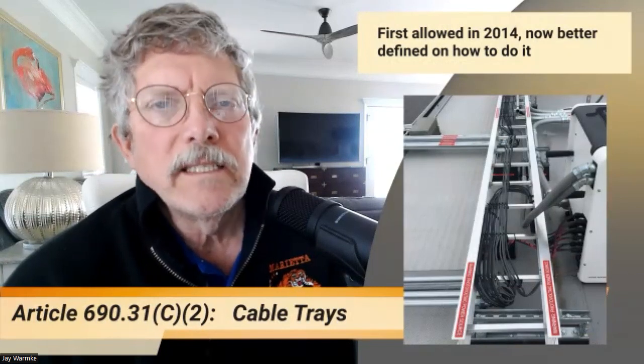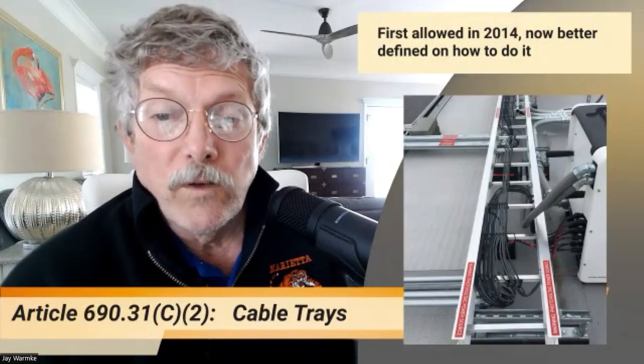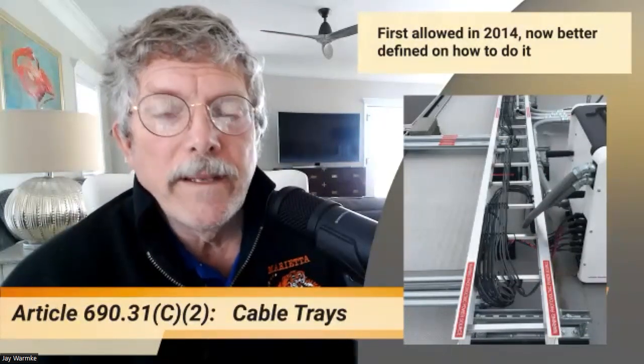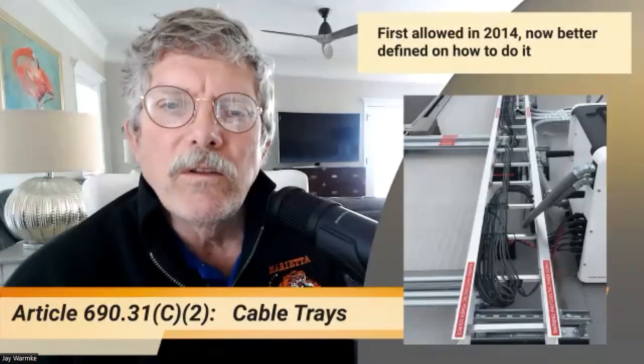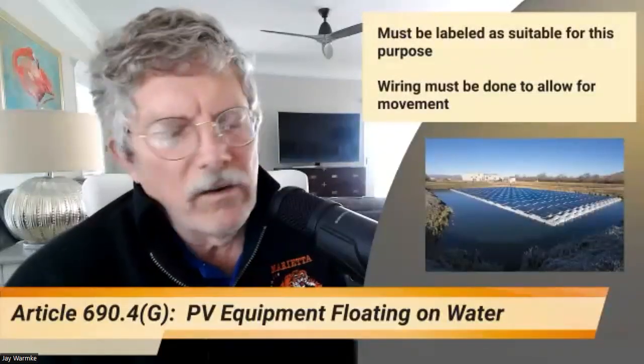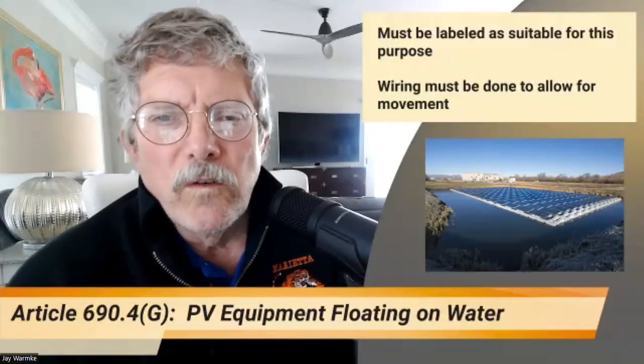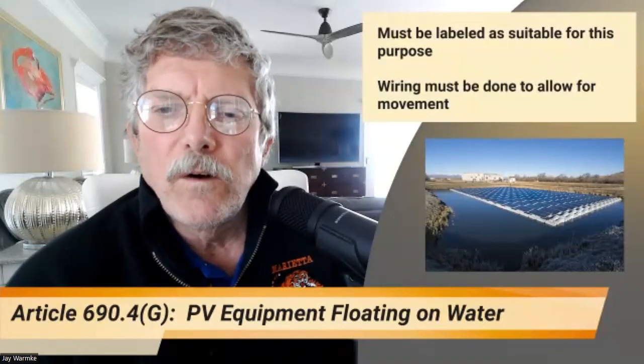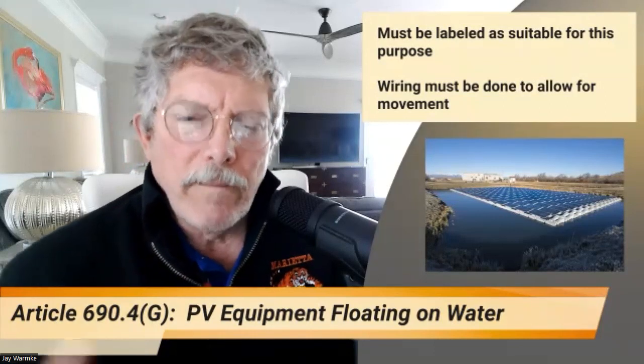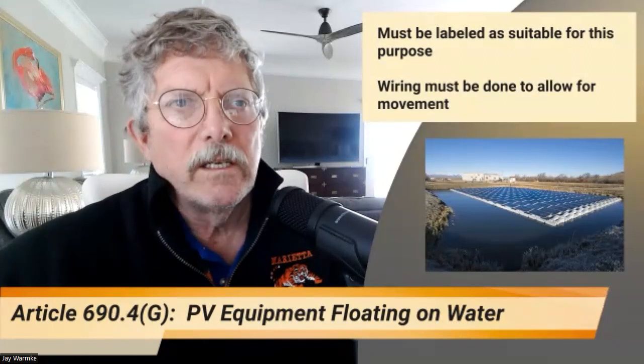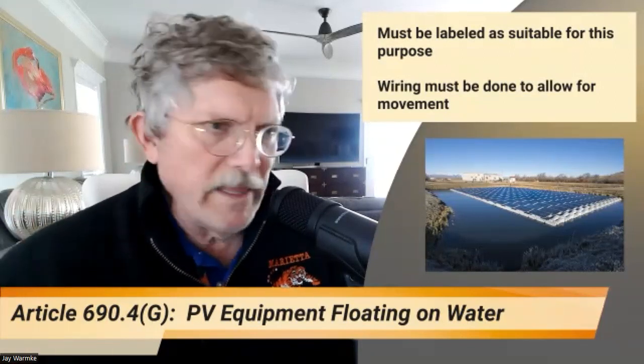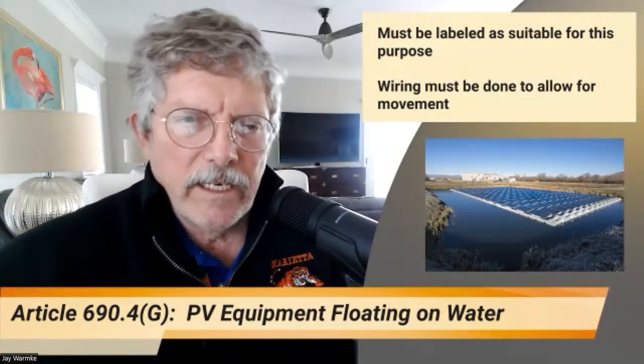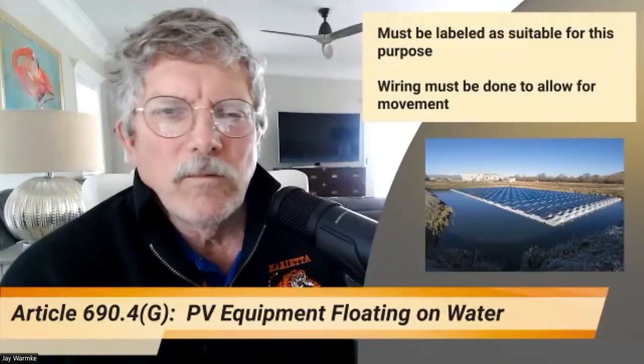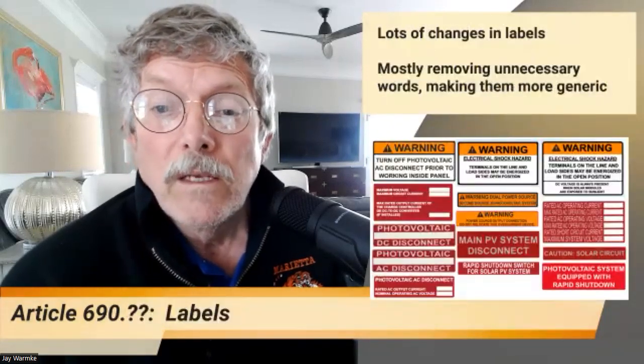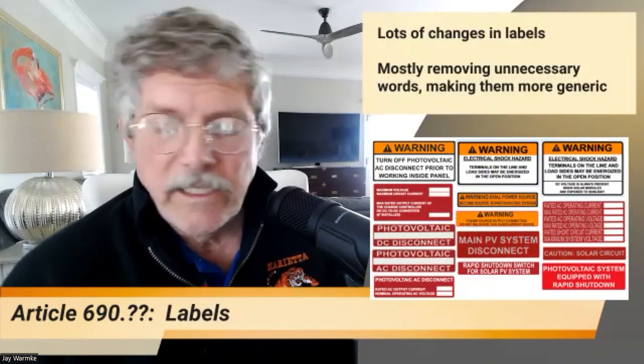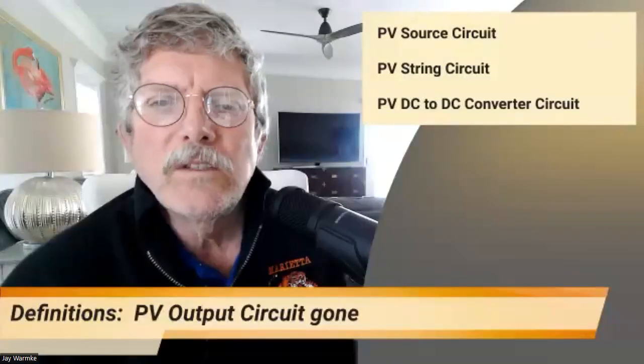They also got into cable trays and discussing how you would install cable trays for photovoltaics. Prior to 2014, we weren't allowed to use open cable trays. You are allowed now, and they're just better defining how those cable trays can be used. A lot of changes. They always love to do this. Changes in labeling. They're just removing unnecessary words. The one that they wanted to focus on a lot has to do with rapid shutdown. The rapid shutdown label was very specific prior to the 2014 code. I mean, if it was the 2014 code, it was a red label with certain wording. After that, the 2017, it was yellow and it had certain wording. Well, now they're saying, listen, it doesn't have to be a specific color. You can make your own label. So that's basically where all the labeling changes are. I didn't think it was worthwhile highlighting each and every one of those changes.